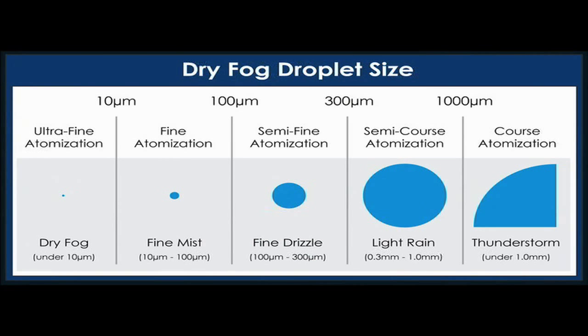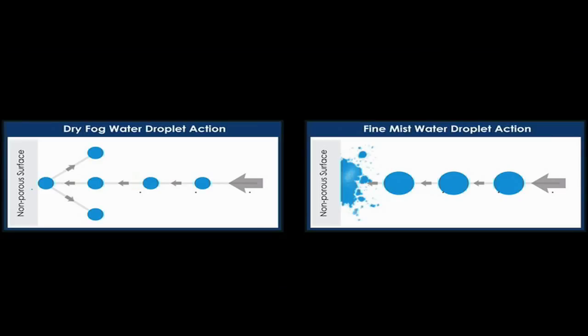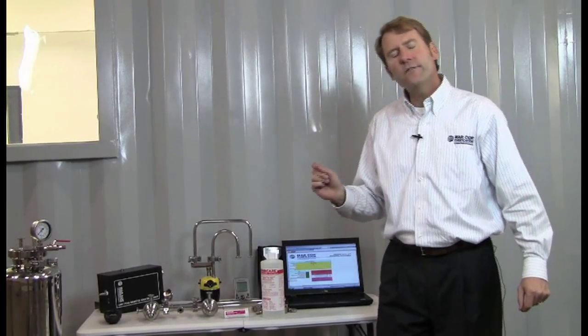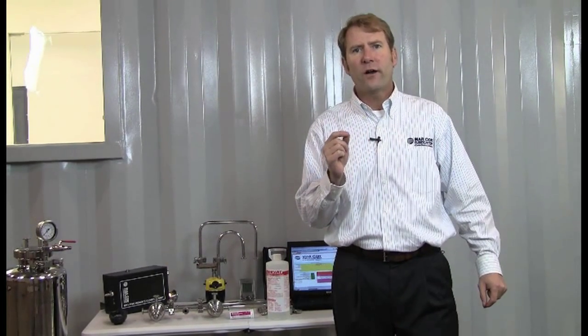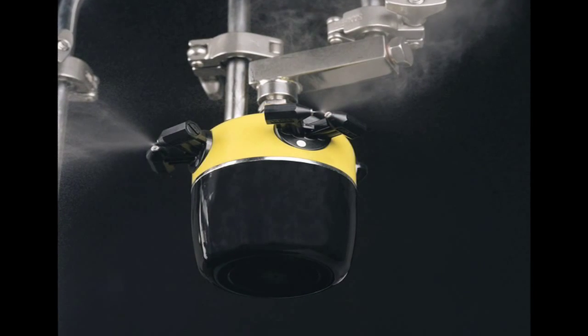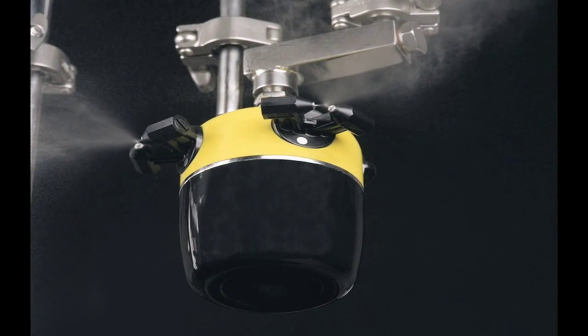The Mar Cor Dry Fog System puts out a 7.5 micron droplet. That droplet is so small it does not wet down surfaces. It bounces off, it evaporates, and it does a vapor phase disinfection, leaving behind no residuals on any surfaces at all. You control the relative humidity in the clean room to ensure that the dry fog has gone everywhere, ensuring complete and total disinfection.